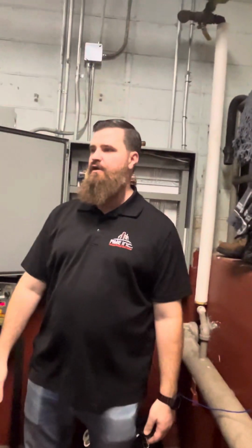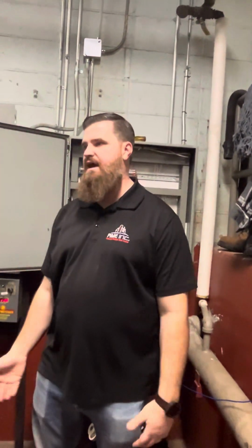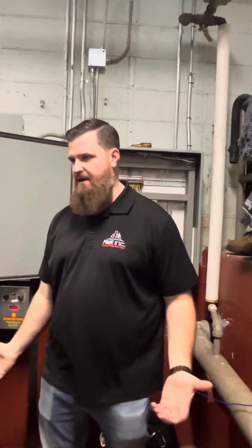It's just picking up status, so that these guys can go, hey, the combustion fan's running, that damper's open, but the boiler's not firing. Why? And that's about it. That's the only thing I would do. And at the same time, we could say, if we turn this boiler on and that damper doesn't open within X amount of time, we generate an alarm, and these guys just know, hey, I need to go check this damper. That'd be about it.